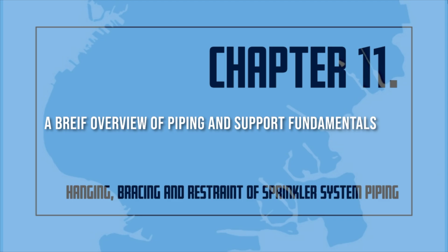A brief overview of piping and support fundamentals. Sprinkler system piping is categorized as follows. Branch lines are directly connected to sprinkler heads. Cross mains or loop mains are directly connected to branch lines. Feed mains are directly connected to cross mains or loop mains. Risers are able to supply feed mains or cross mains directly. The spacing of hangers varies with the material and diameter of the piping, the location of piping connections, ability of the structure to support the piping, the location of the piping in relation to the building structure, and the system attachments. Hangers generally consist of an attachment to the piping, an attachment to the building structure, and a ferrous rod attaching the components together. Hanging components are generally required to be listed devices. However, a licensed professional engineer may also certify that a hanger or hanging assembly may be used.